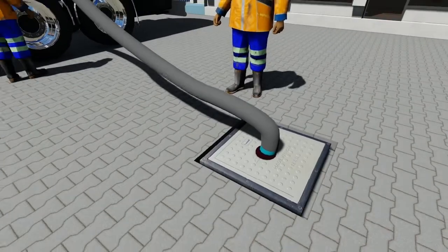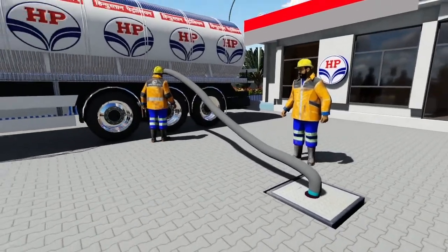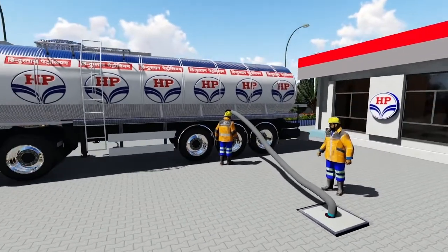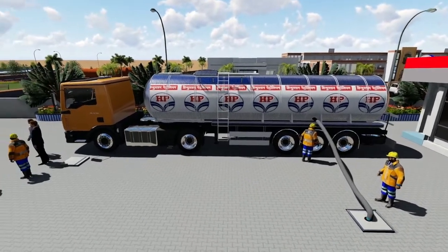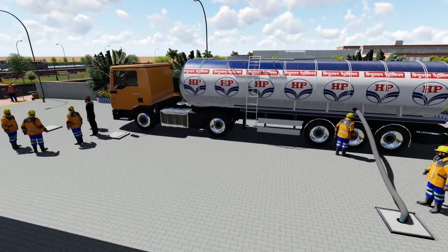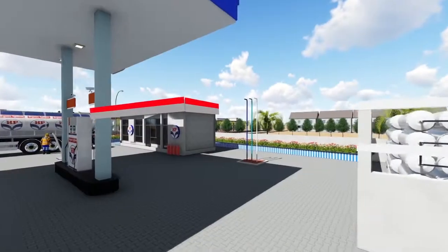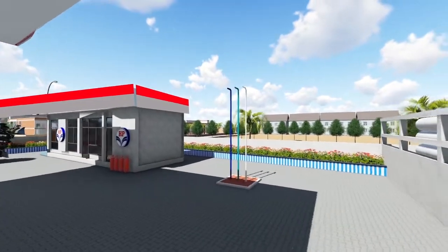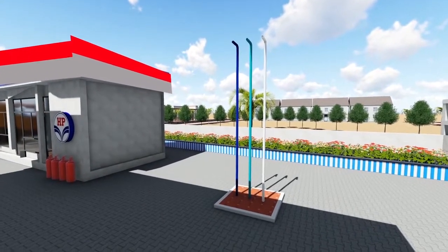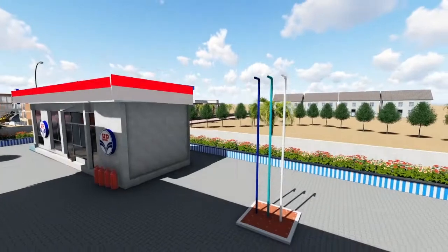We should bring the fill pipes of all the tanks to a single chamber where all the tanks can be filled with fuel by the tanker truck. The tanker should stand in the drive-out position while unloading of fuel. We should bring all the vent pipes together in such a place where we get 4 meters clear area all around. The height of the vent pipe should be according to the PESO norms.